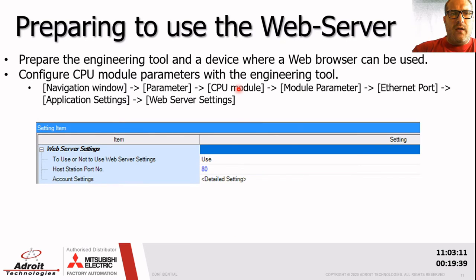Very important, when using the engineering tool, you need to actually enable the web server settings, because by default it's not enabled. You enable it via navigation, parameter, CPU module, module parameter, Ethernet port, application settings, web server settings. Once you've enabled this, you should be able to use your web browser.